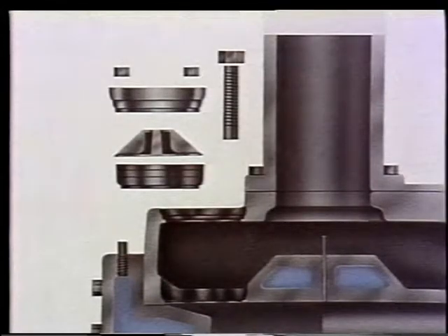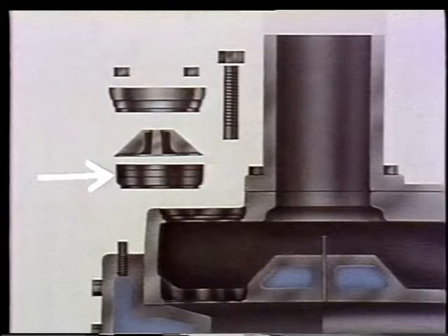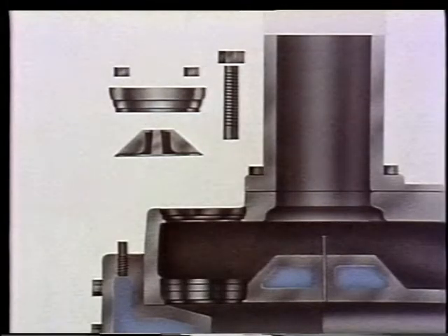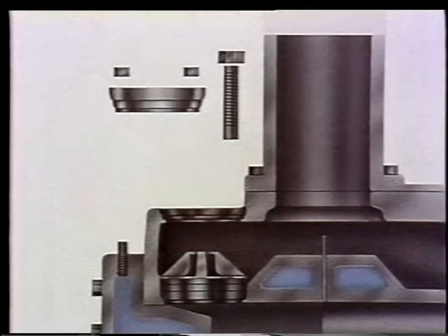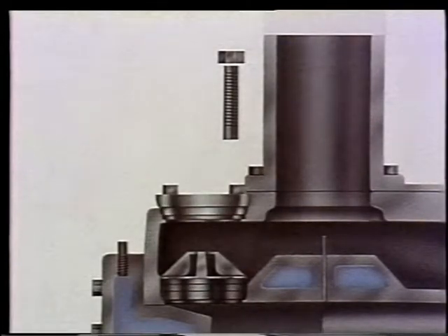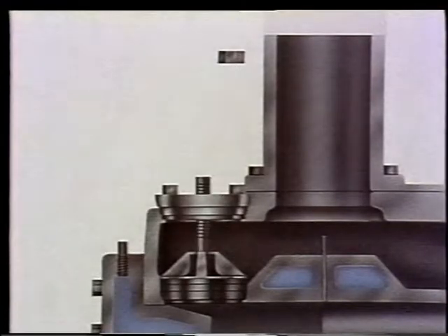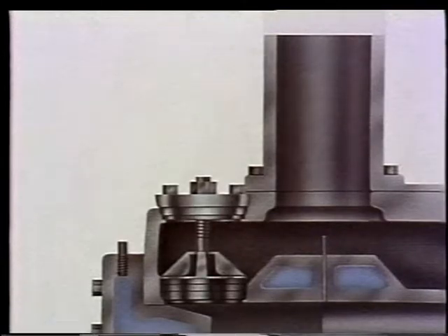Before we can fully understand how this channel valve moves, we need to look at exactly how the valve is positioned in the casing. There are two parts which hold the valve in place: the inner cover, which screws to the valve, and an outer cover that bolts to the cylinder's casing. The outer cover has a bolt which is threaded through the cover and presses on the inner cover to hold the valve in place. There's also a nut on the bolt, which prevents air from leaking out around the bolt.